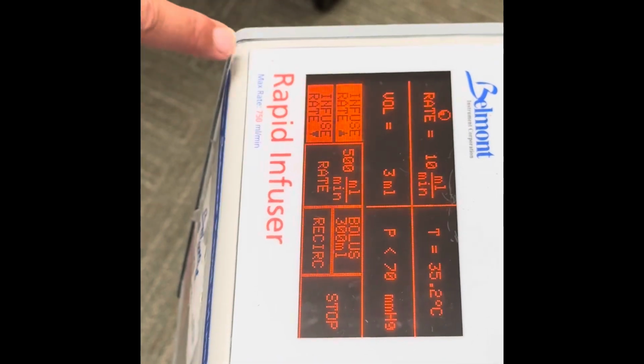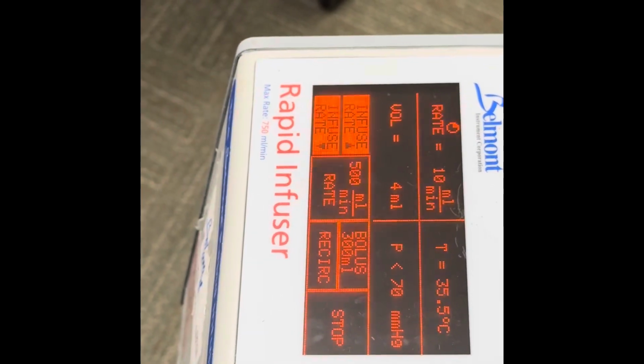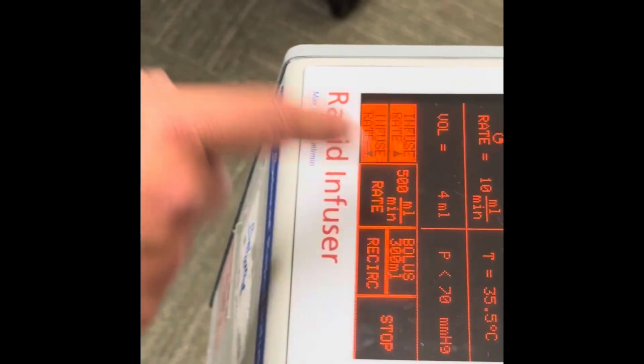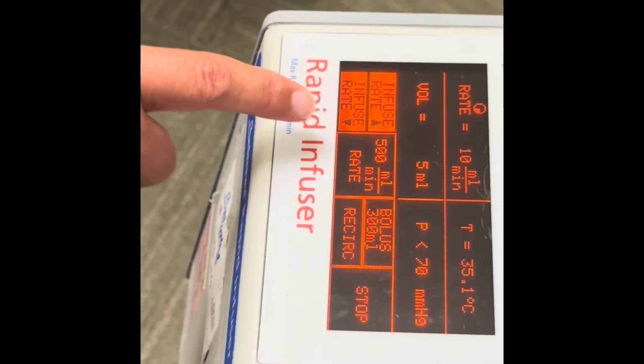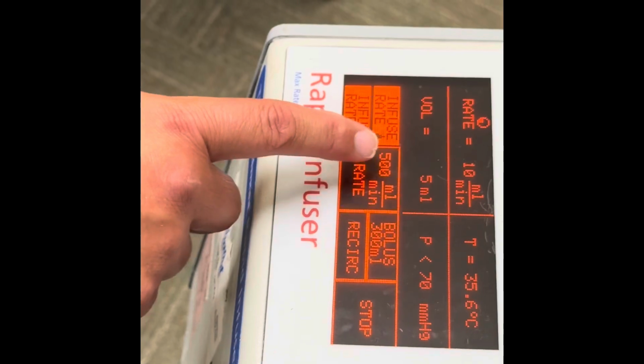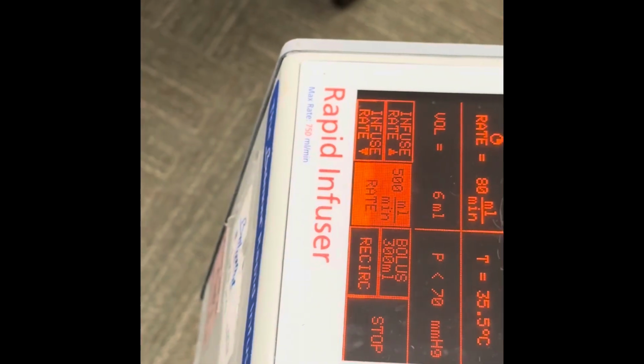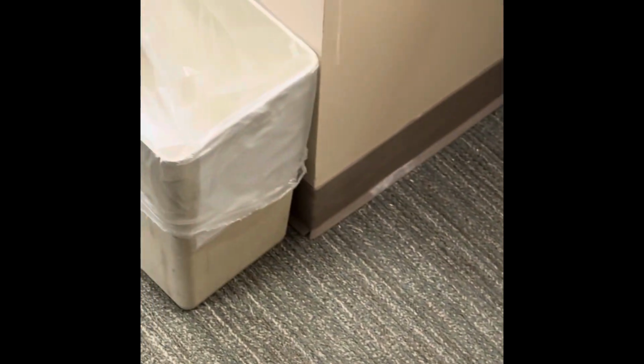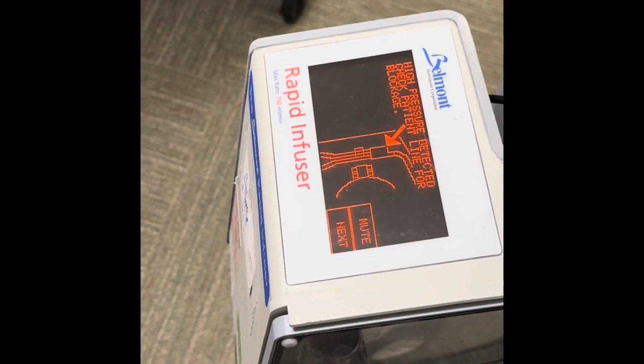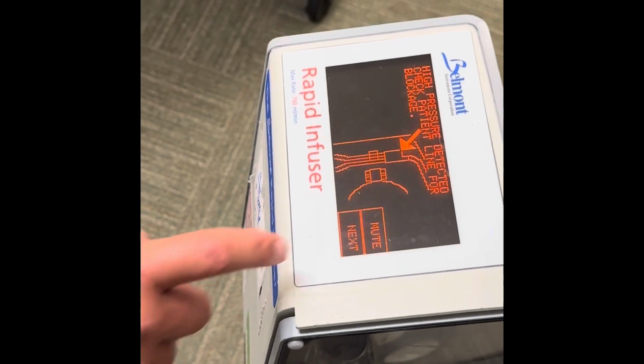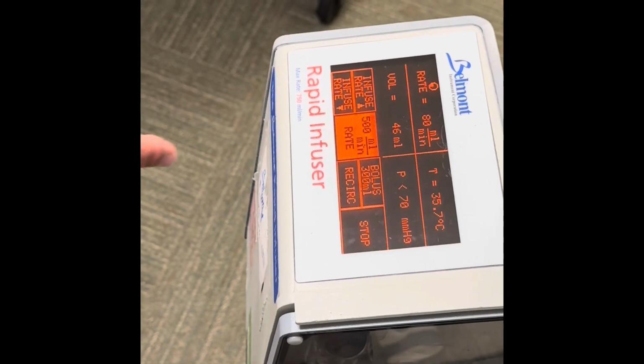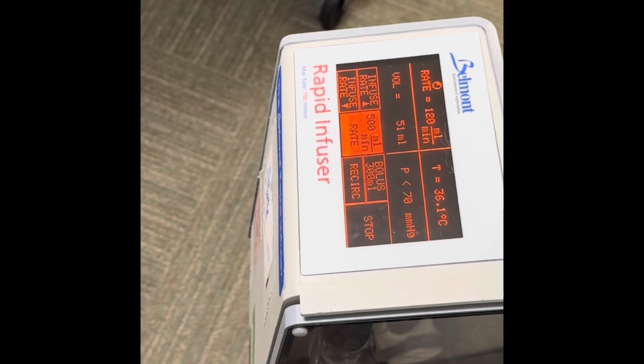We can either adjust it manually, we can do a quick tap of 500 mLs per minute, and that will bolus, or we can just do a quick bolus. I'm going to go ahead and tap 500 mLs per minute because we really want to get this fluid in fast. And as I do that, you're going to hear this machine really kick up. Some of the difficulties I think we've been experiencing is we get a high pressure alarm, which I'm going to trigger to happen. And so you can see here it says high pressure detected, and that's because I squeezed the line. So when I let go of that, I can hit next, and it's going to resume what I had asked it to do before.